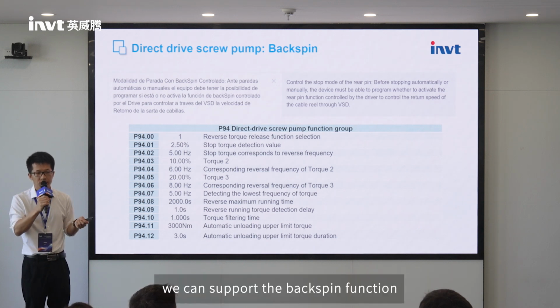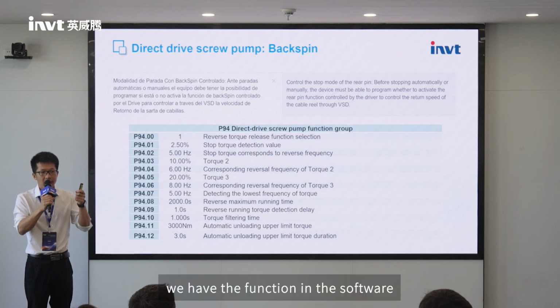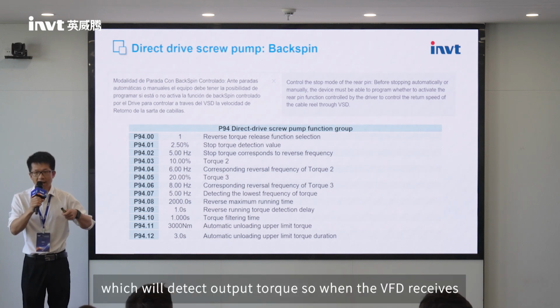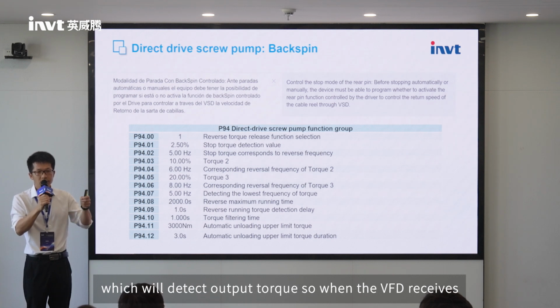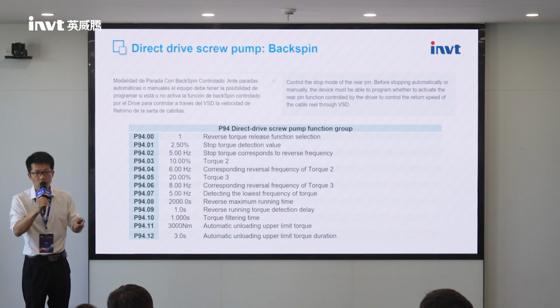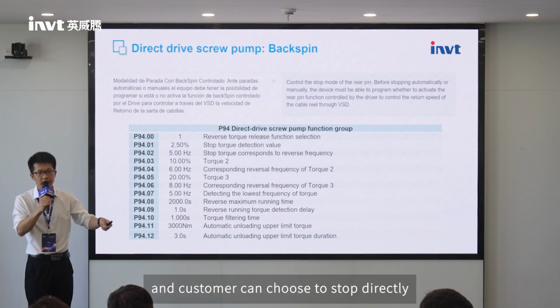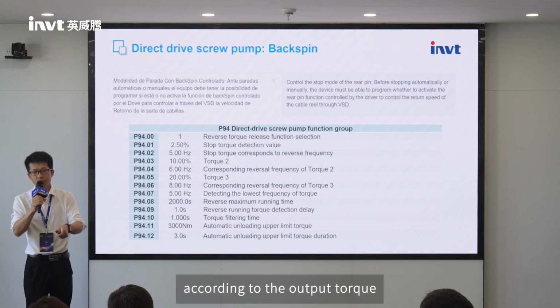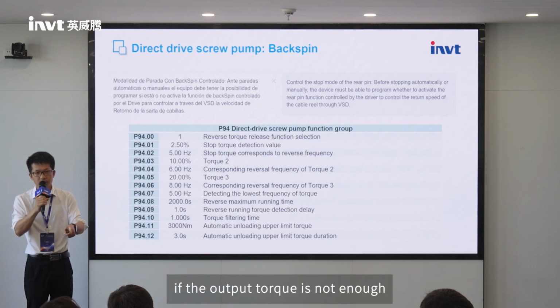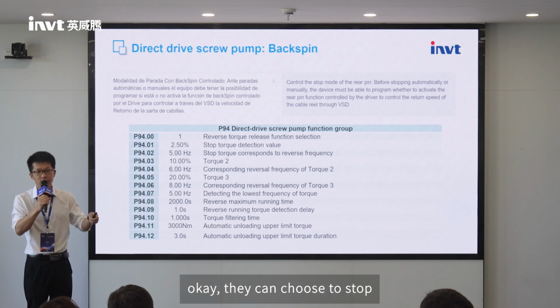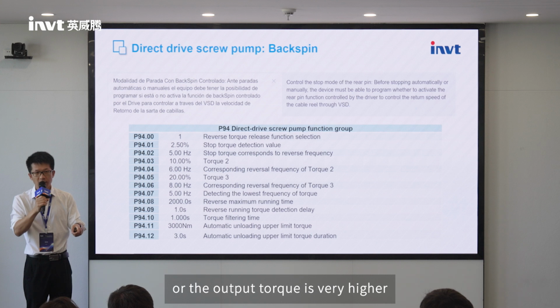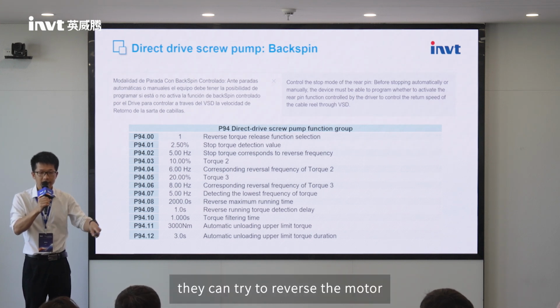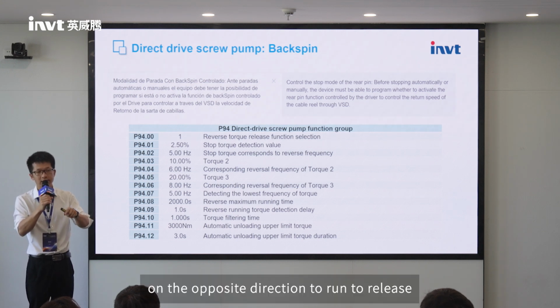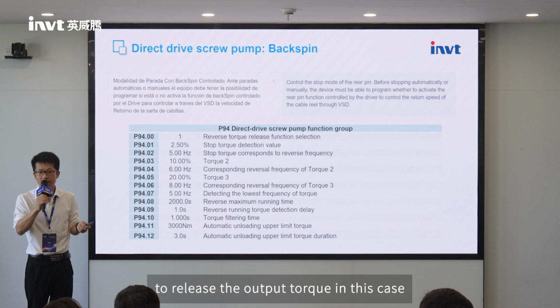We support the backspin function with software that detects output torque. When the VFD receives the stop command, it detects the output torque, and the customer can choose to stop directly if the torque is not enough. If the output torque is higher, they can try reversing the motor to run in the opposite direction to release the torque.